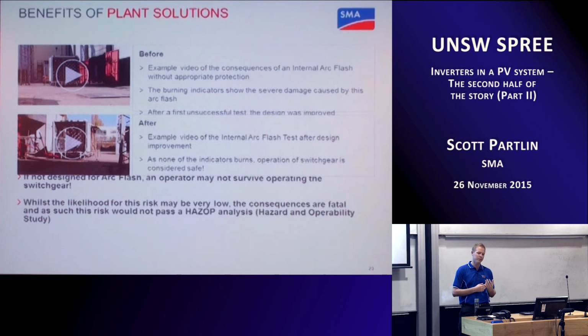And so that introduces safety concerns. Now, the advantage in these sorts of applications of a central inverter, and being able to be integrated into a plant solution, is that you can include things like arc flash protection. If you deploy these assets here and the transformers there and the switchgear here, and you bring it all together, that's not something you're able to easily do, and it's also not something that's type tested according to international standards.